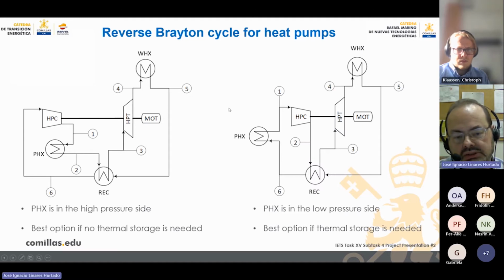However, we can plot another layout where we have moved the product heat exchanger from here to here. What is the advantage of this layout? In this case, both heat exchangers, the waste and the product heat exchanger, are in the low pressure side. This is important because if we want to use a thermal energy storage system with molten salts, with hot air, with pebble beds or something like this, in this heat exchanger, the CO2 in the pipe has the lower pressure, 20 bar, 40 bar, 80 bar, more or less, but not the maximum pressure of the cycle. So this heat exchanger can be a conventional heat exchanger, and we can use molten salt or air in the secondary fluid without any limitation.